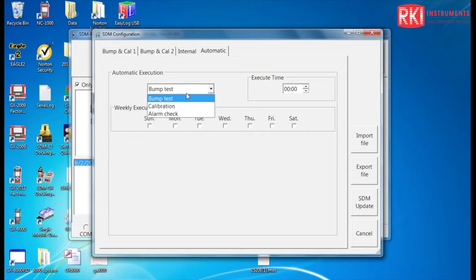If you want to bump test or calibrate, you can set them up to calibrate every Sunday at 1 o'clock a.m. And it will then go ahead and do that at that time. So when the guys come in the morning to pick up their instruments, they're going to all be done, turned off, charged, ready to go. That's kind of a cool feature that we didn't have in the other docking stations.